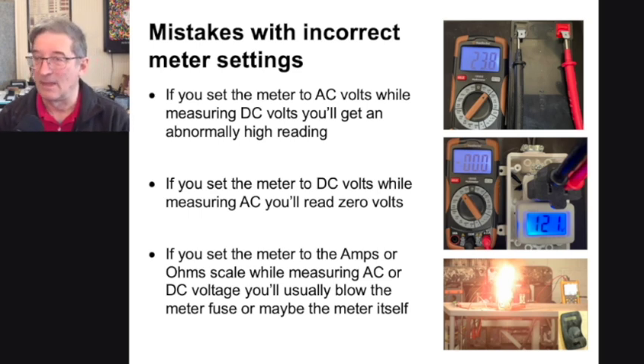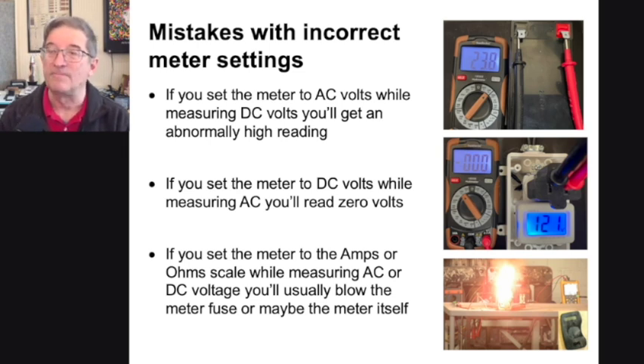Third thing: never set your meter to the amps or ohm scale while measuring AC or DC voltage. Usually you will blow the meter fuse, but I've seen a couple of meters up close where they were the super cheapest Harbor Freight meters, plugged into way too high a voltage, or put onto the amps range across a 120 volt circuit. The meters can actually explode.